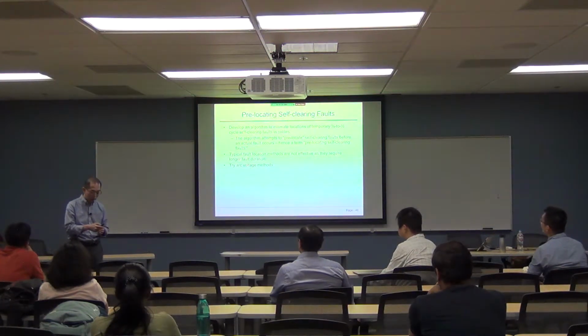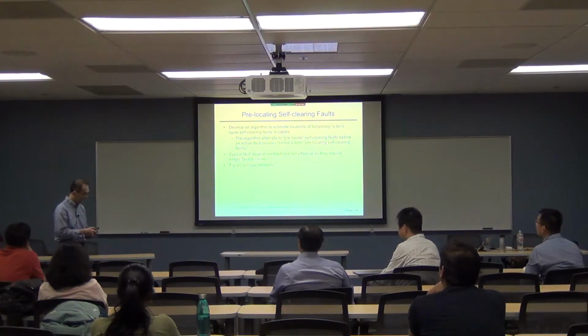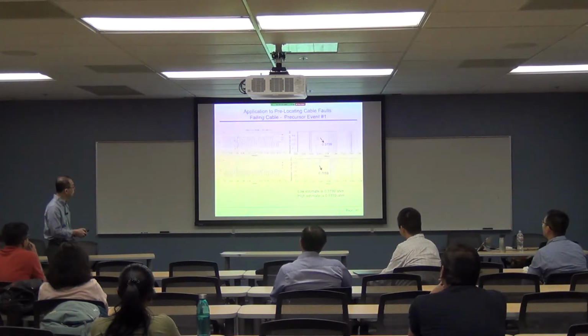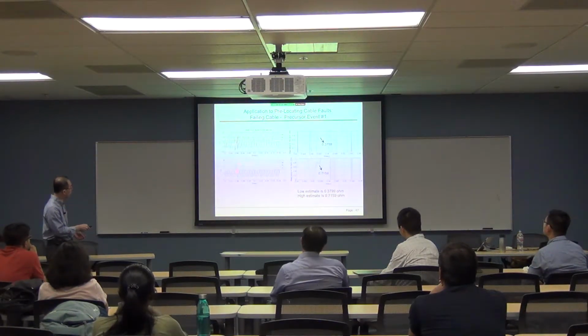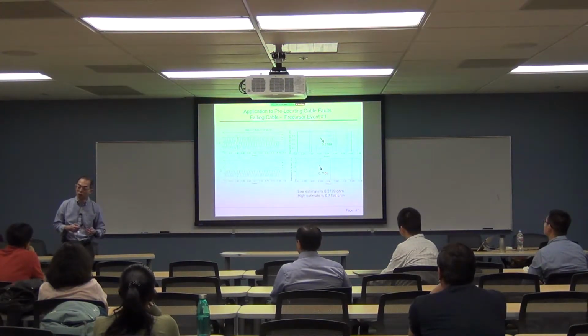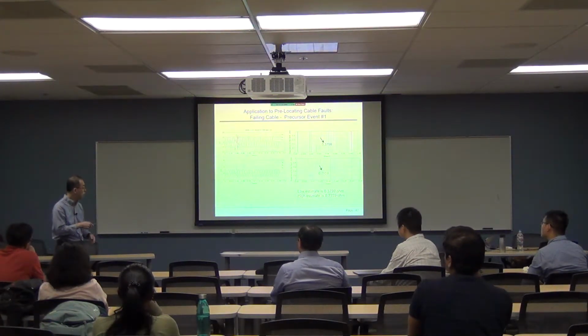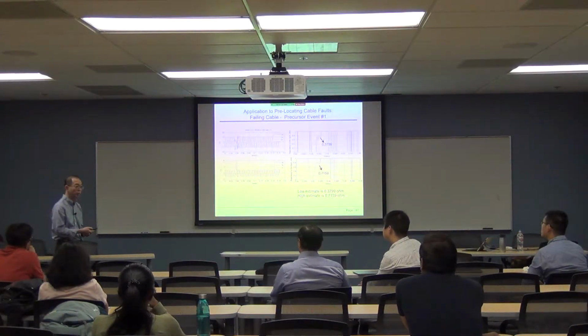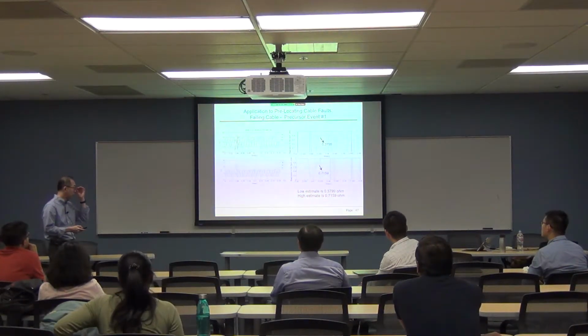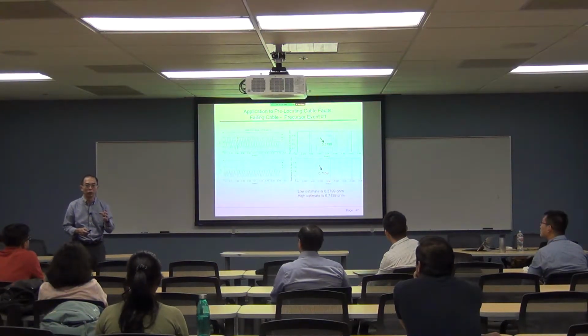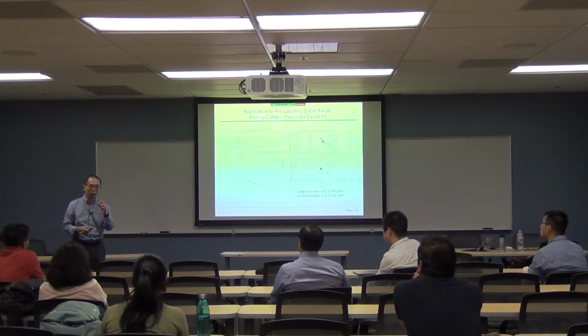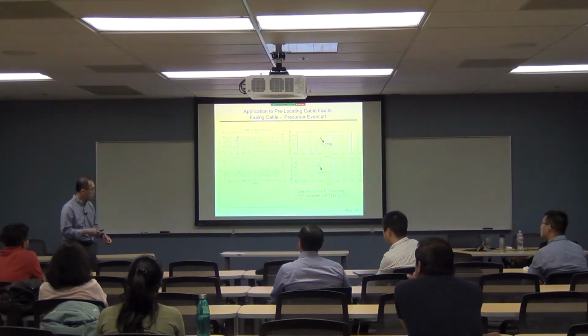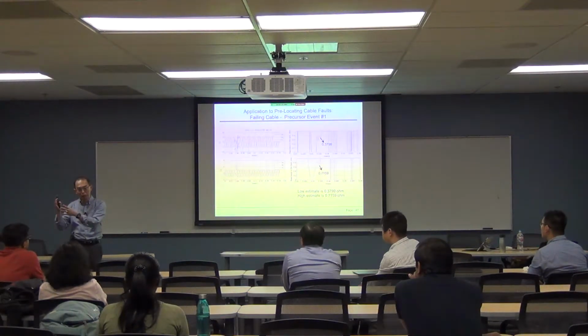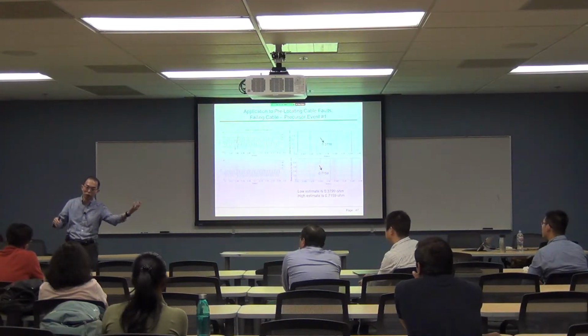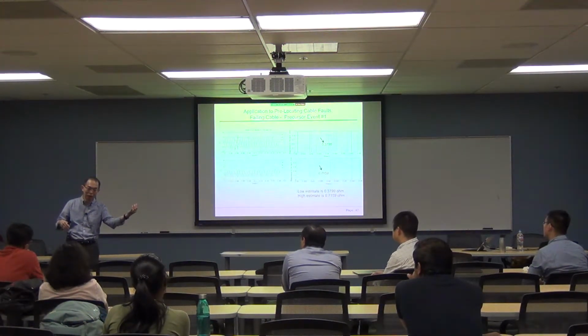But the most difficult one is to figure out where the fault is, okay? So what we want to do is to figure out, when this fault happens like this, where is the location of the fault? Can it actually be done? We doubted ourselves whether we could ever do that. And apparently we can. We finally have that happen. The key goal here is that we need to estimate the arc voltage. So you can see that the monitor is at the substation, and the fault is somewhere along the line under the cable.